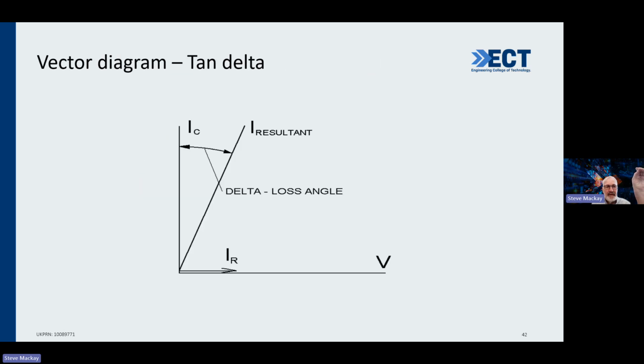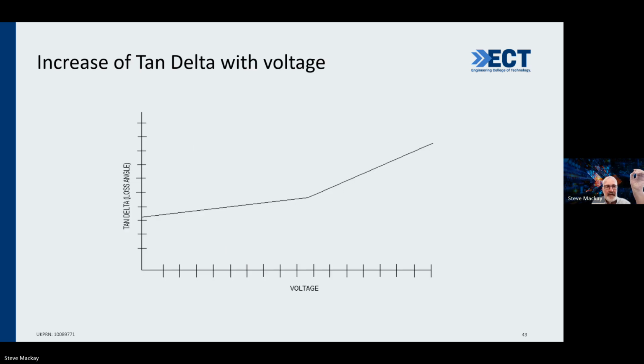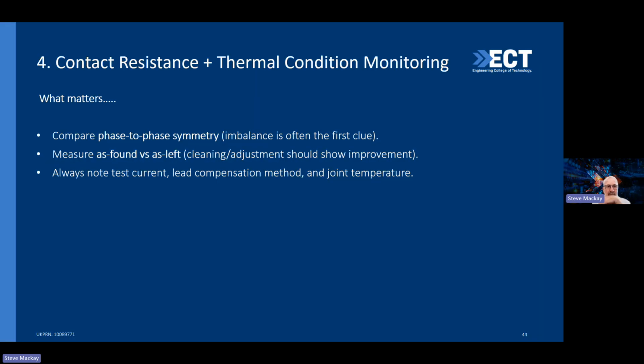Cracked bushing. So obviously the tan delta is really important. And here's an example of your testing with tan delta with voltage. Really important. Contact resistance and thermal condition monitoring. You compare the phase-to-phase symmetry. So obviously if you have 150 amps in each phase, but the third phase is 80 amps, there's a bit of a problem here. So you may say, hey, there's something to look at.